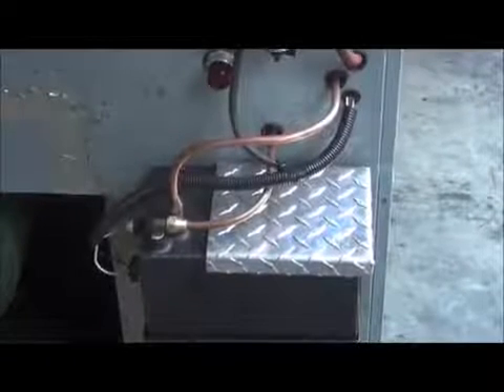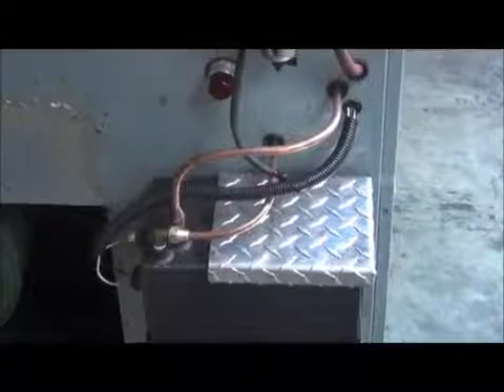My old one used to siphon oil directly out of this tank, and it took so long to actually get to the nozzle that on a really cold day it was already cold by the time it got to the nozzle, and it wasn't burning quite as efficiently. Now, this tank also has a float switch in it. As the level goes down, as the furnace uses oil, the float switch engages a relay inside the furnace that turns on an external oil pump from whatever tank is supplying this to pump oil back into it. And it cycles on and off just a couple times every hour.